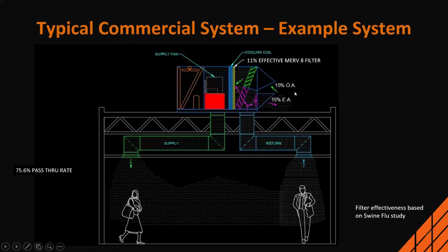Most of the time, we're going to be bringing in about 15% outdoor air, and typically a MERV 8 filter as a baseline filter. And that 15% outdoor air means we're also going to be exhausting 15% of the air. So if this is our carrier over here on the right-hand side, and we're bringing the virus in here, and we're going to exhaust 15% of the virus particles, and bring in 15% outdoor air, then we're going to capture 11% of the virus particles.